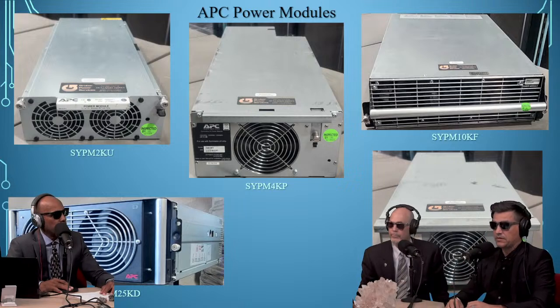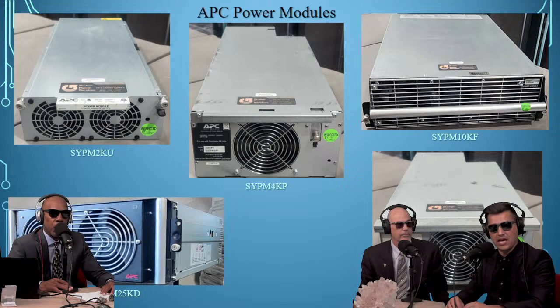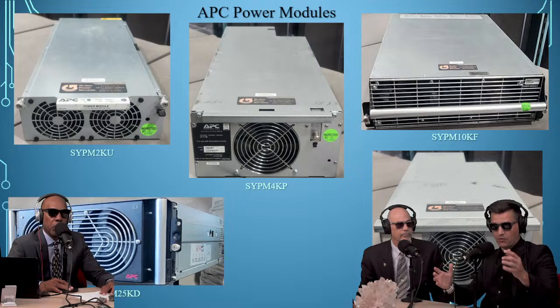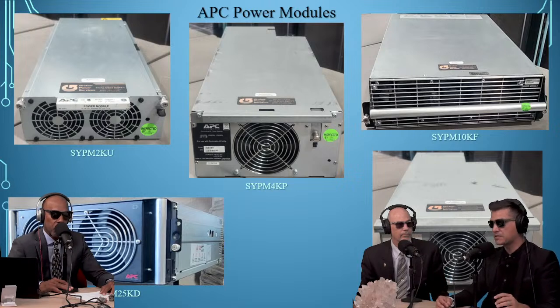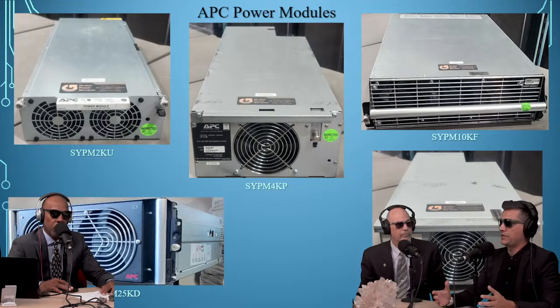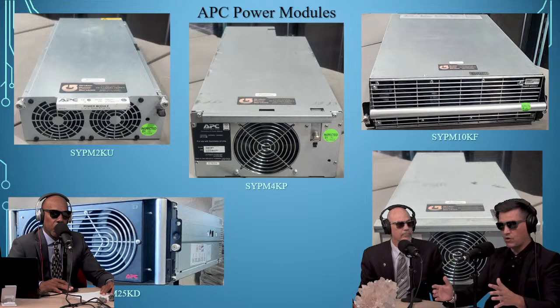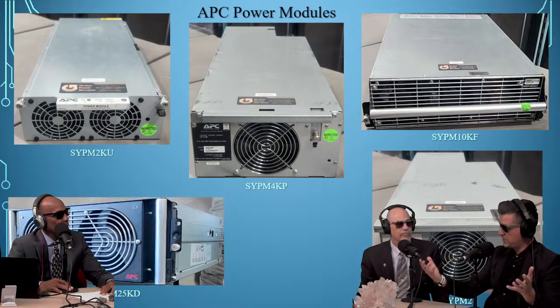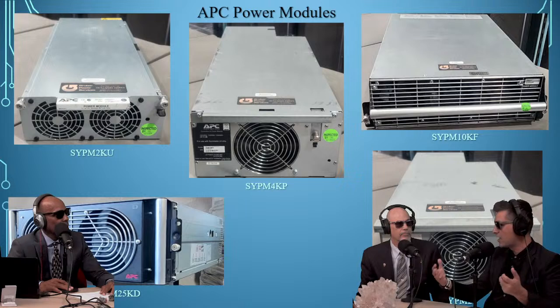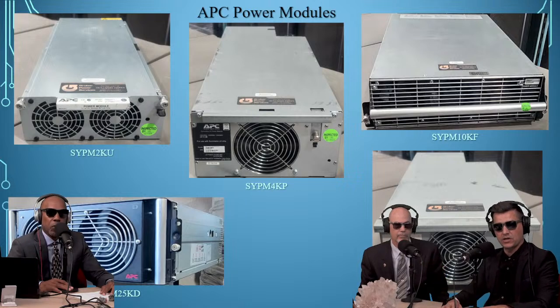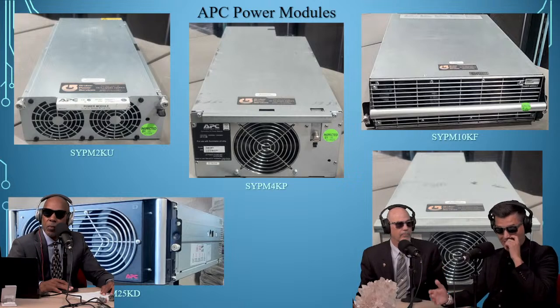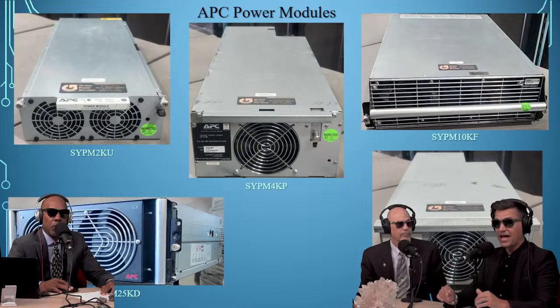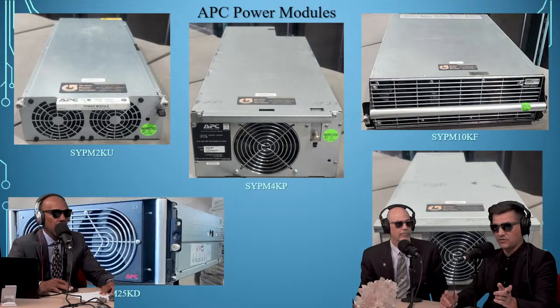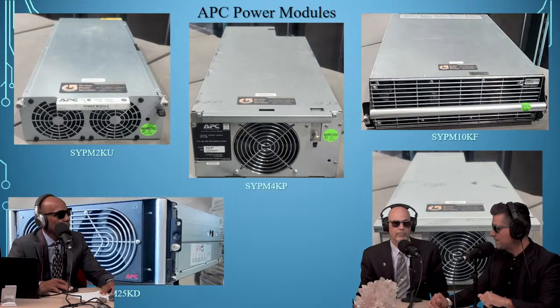Elvis actually sold how many? I sold 15 of them because it's 67 kVA per power module, humongous, and there's 3 inside a box to give you, I think, 200 kVA in one box, and 5 of those is 1,000 kVA, so it's a megawatt. I've sold that to a customer, and that's the largest that I've come across. But I just experienced something in that realm when I was at a customer site this past week.